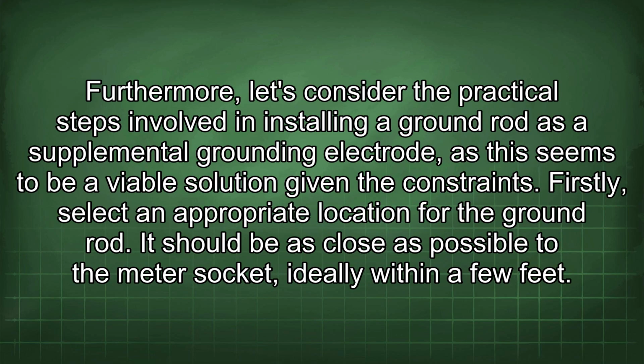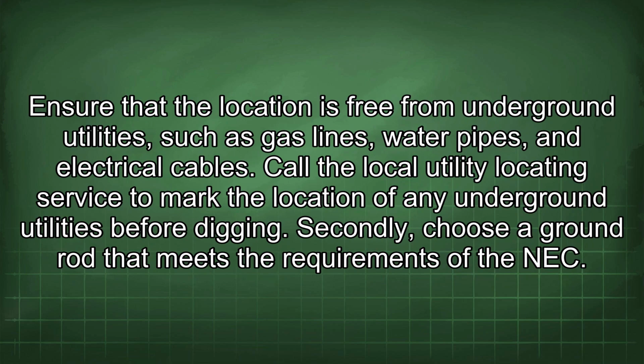Furthermore, let's consider the practical steps involved in installing a ground rod as a supplemental grounding electrode, as this seems to be a viable solution given the constraints. Firstly, select an appropriate location for the ground rod. It should be as close as possible to the meter socket, ideally within a few feet. Ensure that the location is free from underground utilities, such as gas lines, water pipes, and electrical cables. Call the local utility locating service to mark the location of any underground utilities before digging.